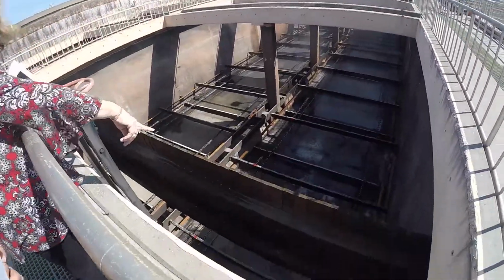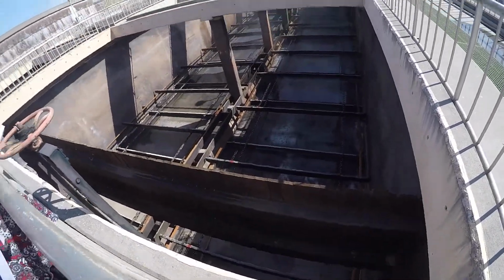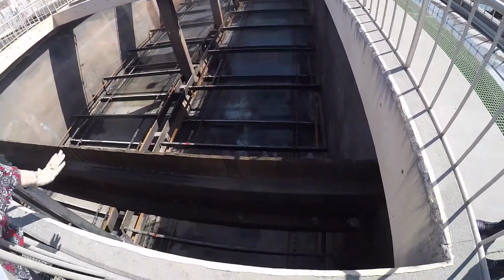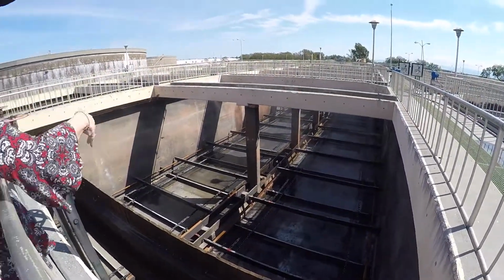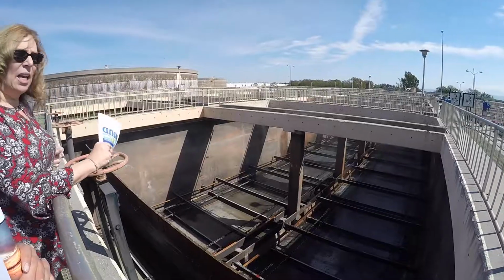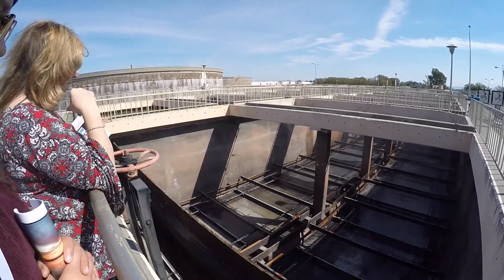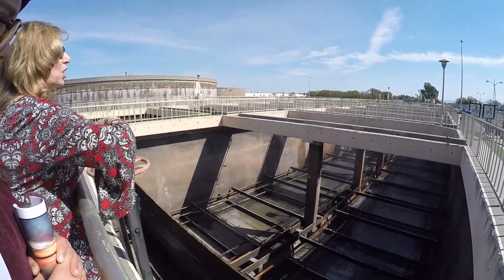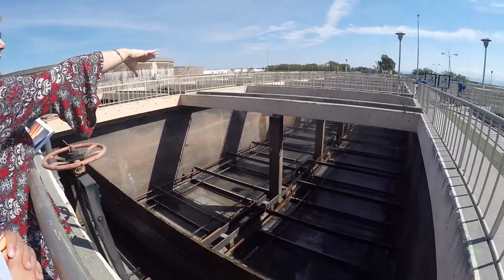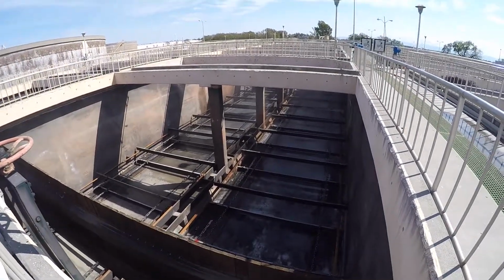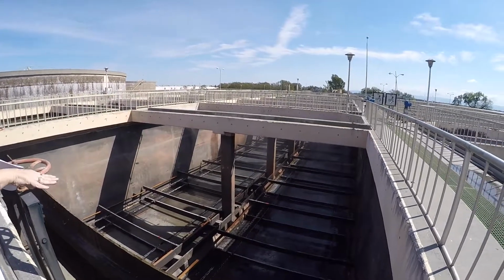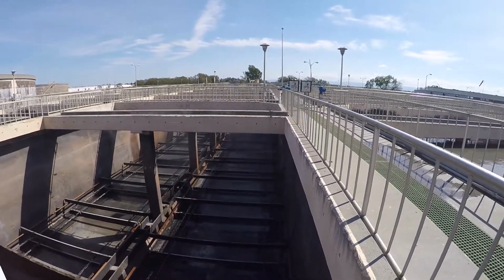The reason it looks like a little fence is because of the velocity of the pumps, they push the water. What this will do is it'll slow your water down, and it causes more of the solids to drop and the water to go over the top. And what those do is when the primary is working, they rotate. So when the solids fall, they move the solids back, and the solids leave here and either go to the digesters or they go to the belt press for solids. And then the water flows over and goes into the secondary.